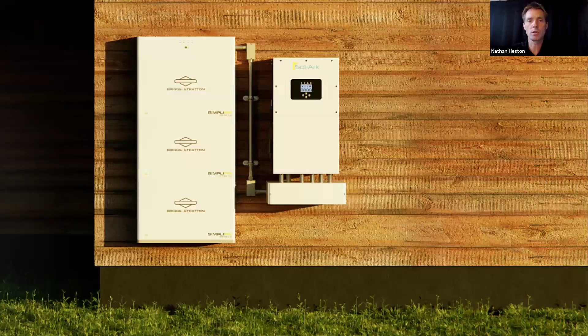I'm showing it with our 6.6 batteries. Yes, that conduit is undersized—it looks like 3/4 inch conduit, but what you really want to use there is 2-inch conduit. This is a marketing photo; I wish I had the skills to update that conduit with Photoshop.